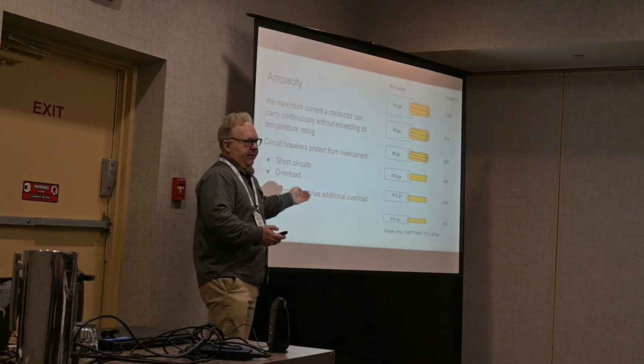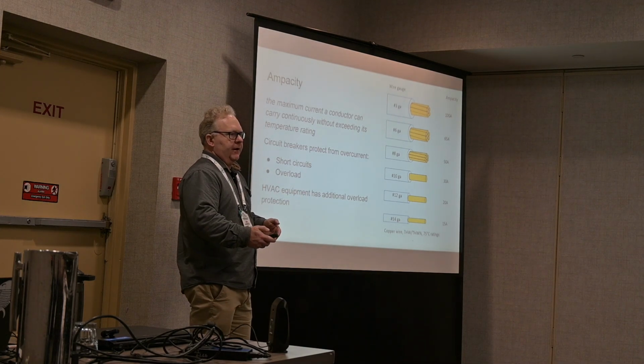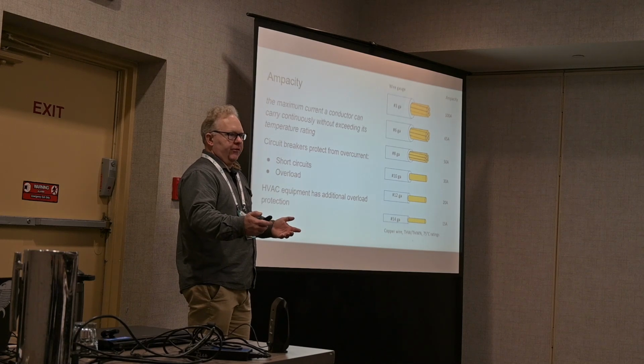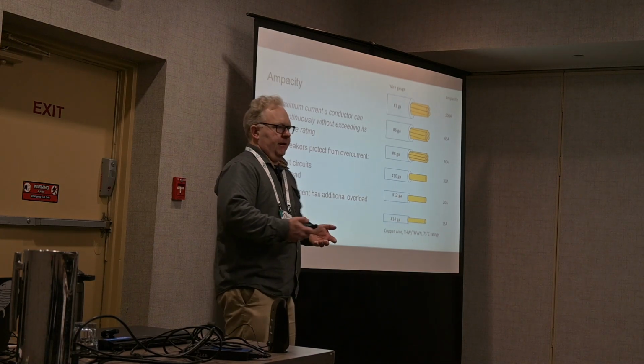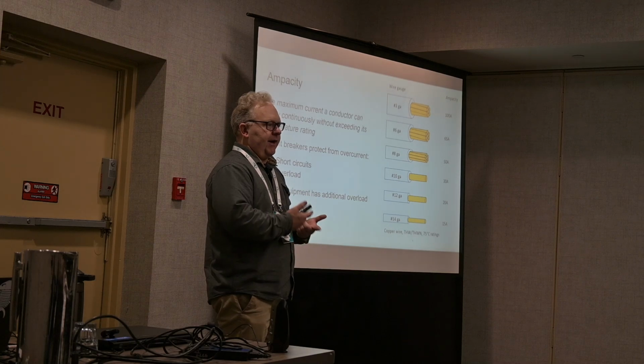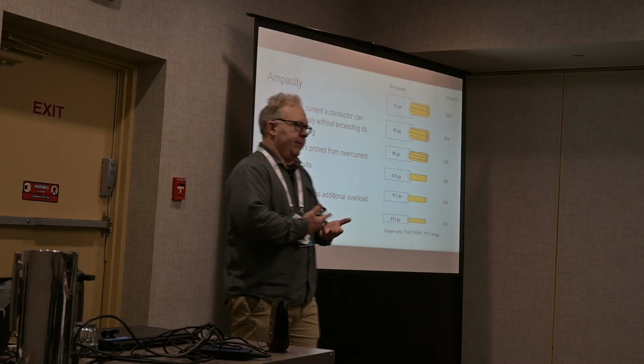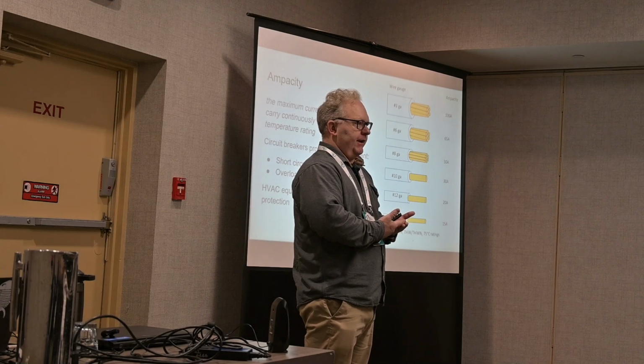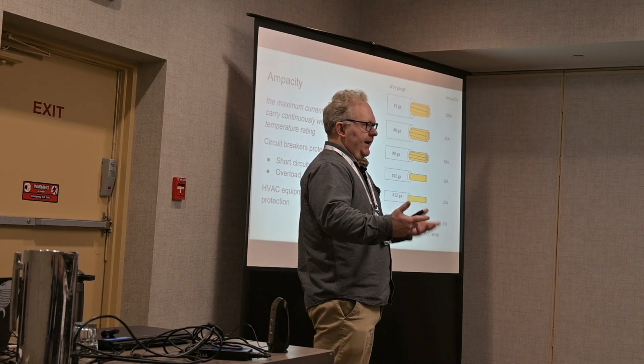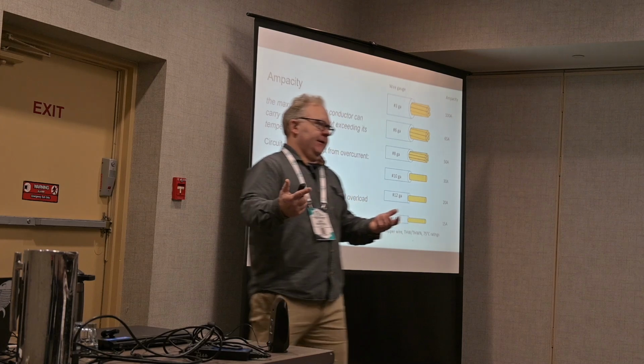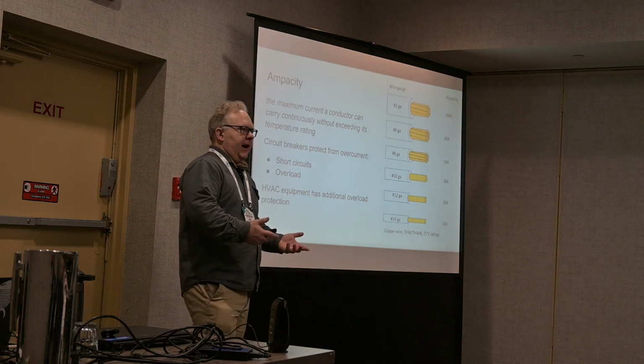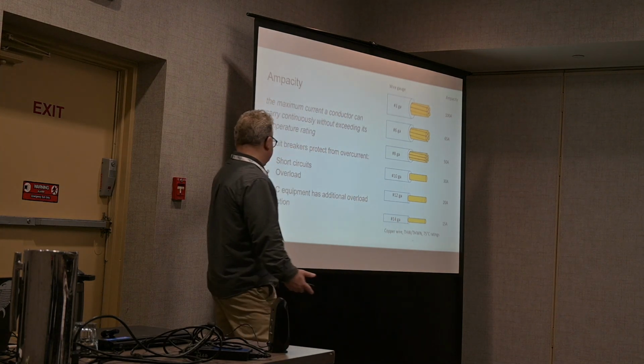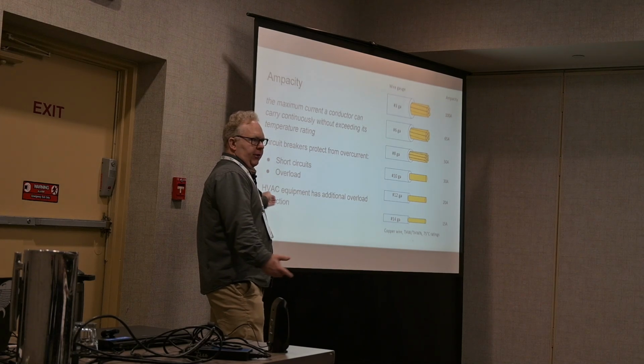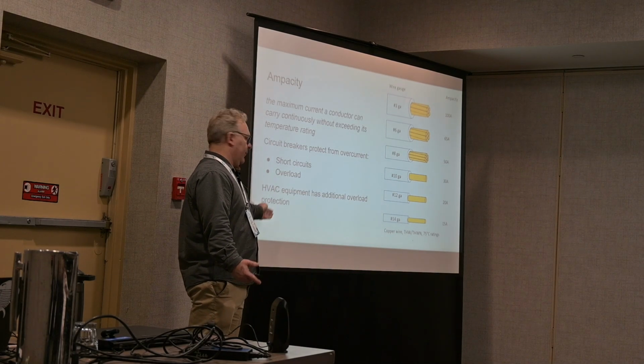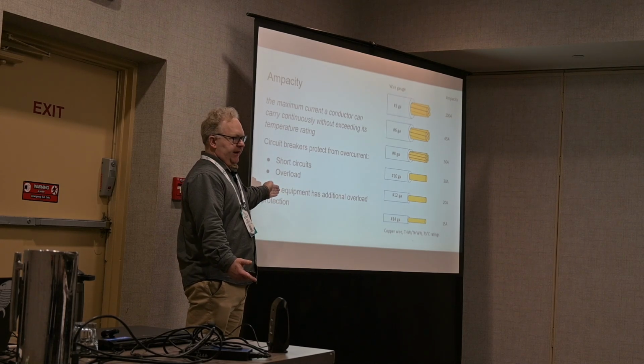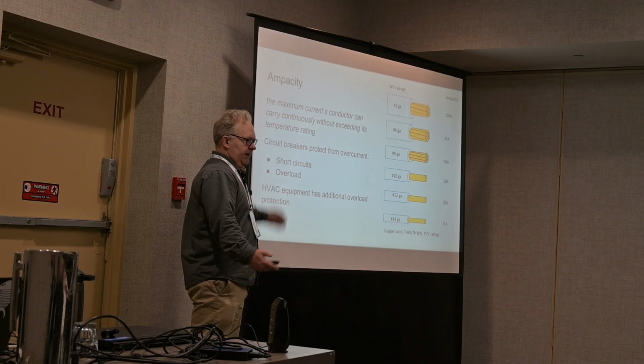Breakers will also shut down in the case of overload, meaning more of a continuous overdraw. An example of when I've done this is when I had my coffee maker, my toaster, and my microwave all plugged into the same circuit. That was a 20 amp circuit drawing probably 30 amps of power. The breaker trips to prevent overheating. It's also important to know that HVAC equipment has additional overload protection built into the equipment to protect both the equipment and the conductors.